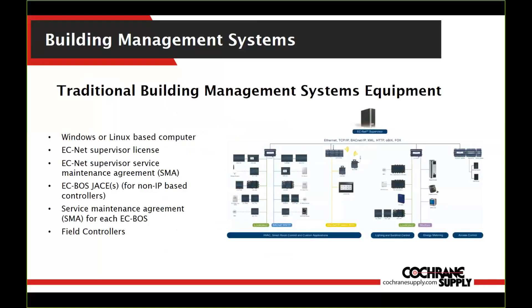This is a typical architecture we see in a lot of buildings for a traditional BMS. On top, you have some sort of PC, Windows or Linux — it could be a physical PC, rack-mounted server, a virtual machine, or even a solid-state industrial PC. You'll need a license for supervisory software for EC-NET, a maintenance agreement for that, and typically an EC-BOS in the system used for field bus integration, whether it's LON, BACnet MSTP, or Modbus RTU, along with a service maintenance agreement for that BOS and the field controllers required for control of all the equipment, both plant and terminal.